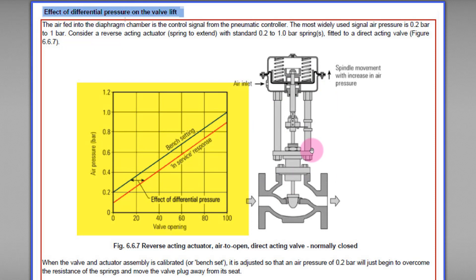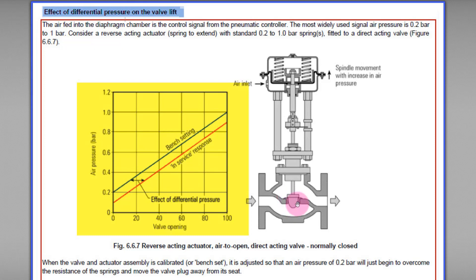However, when we install the same control valve in the field, the result may be slightly different from what we get in the workshop. The red curve shows the in-service response in the field. During process operation, a differential pressure exists across the valve port — the difference between upstream and downstream pressure. This differential pressure acts on the valve plug and tries to push it upward.